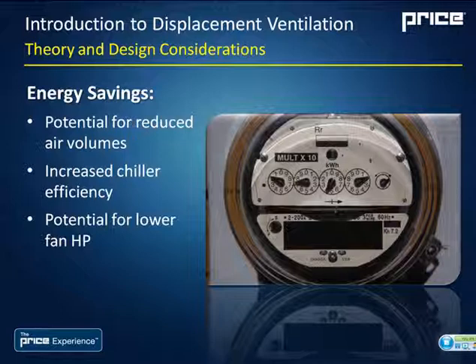And because of the potential for reduced air volumes and reduced static pressures, reduced velocities throughout the system, there is a potential for lower fan horsepower as well. So smaller equipment or reduced sizing of the fan equipment as well.